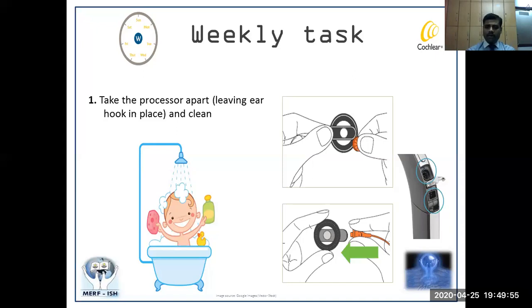Please make sure that every week you remove the magnet, clean it properly, and refix it. At the same time, remove the cables and clean them. We want you to remove the cable once a week because it has two ends - one goes to the sound processor, the other to the transmitting coil. Both ends, especially the one connecting to the transmitting coil, may attract dust because of the oil, and the socket at the sound processor attracts dust due to sweat. So be very careful when cleaning it. Clean both ends using spirit or alcohol swabs on the hinges, and use a brush to clean it.